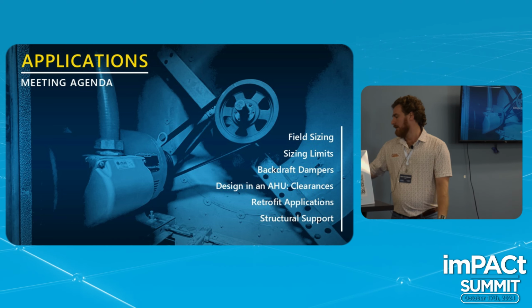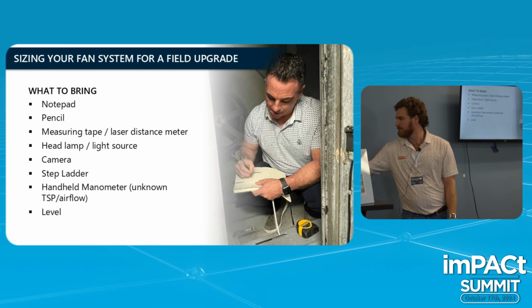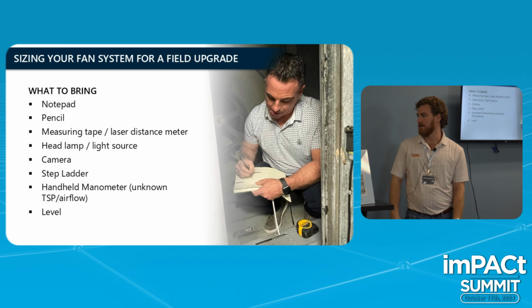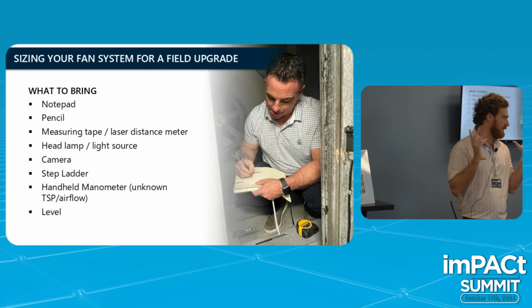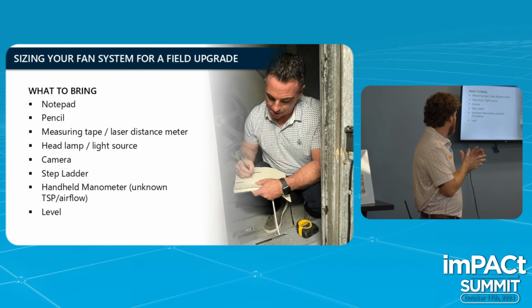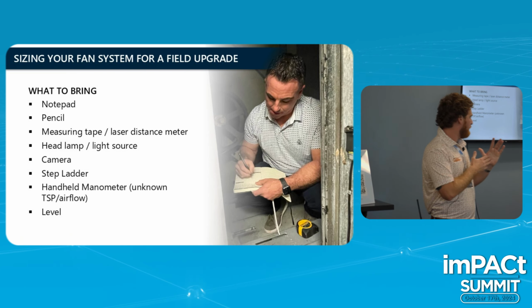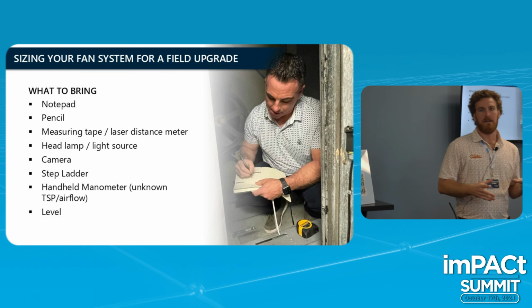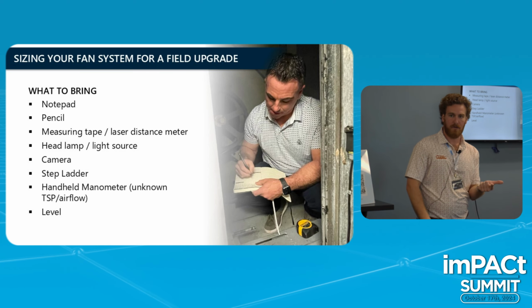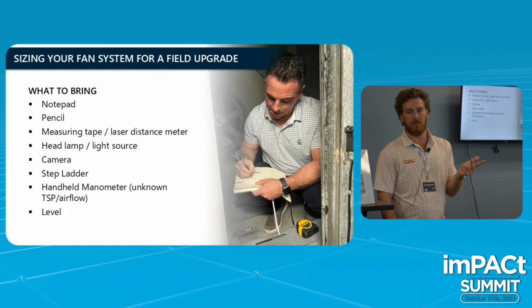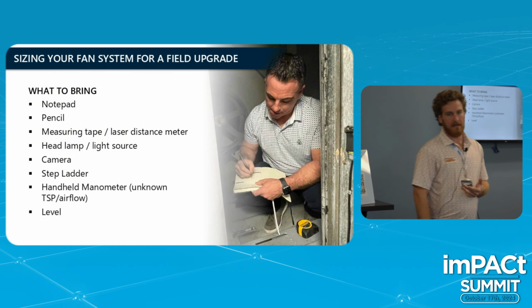So, the first thing is to make sure you have all these measurements when you go into the field. You want to get CFM, total static pressure, the interior width and height of the unit, and the supply voltage.